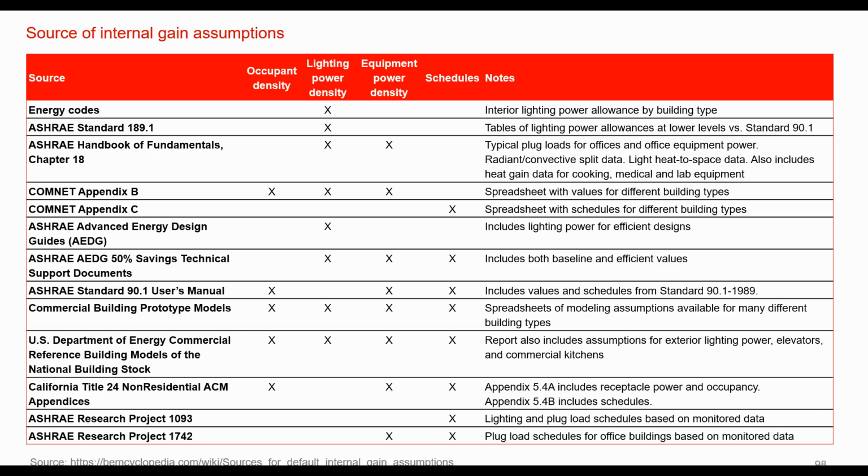And then schedules, again, for a compliance model, you really just want to make sure you're using schedules that are realistic. And you have to use the same set of schedules in both models. As long as you're not varying the schedule types, you're following the guideline to show compliance for energy code.